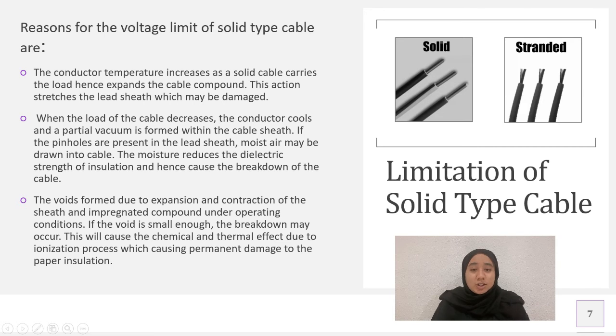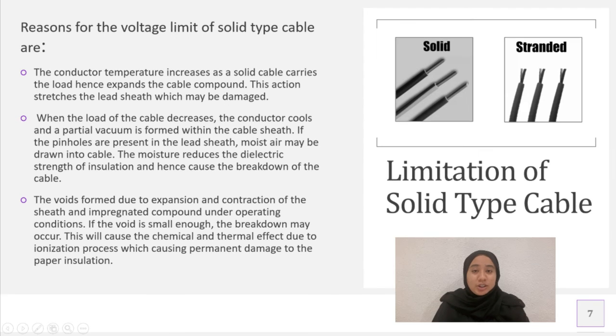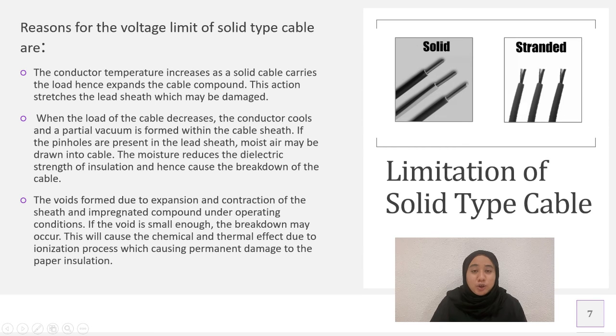So the first reason is, as a solid cable carries load, the conductor temperature will increase, hence causing the cable compound to expand. This action will stretch the lead sheath, which may be damaged. The second reason is when the load of the cable decreases, the conductor temperature will cool down and a partial vacuum will form within the cable sheath. If pinholes are present in the lead sheath, moist air from the surroundings may be drawn into the cable. This moisture will reduce the dielectric strength of the insulation and hence cause the cable to break down.